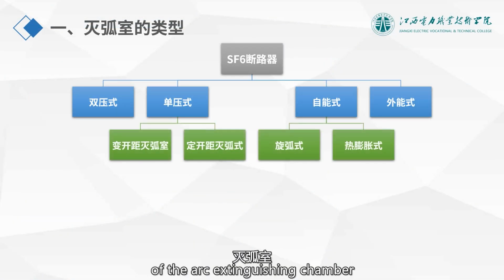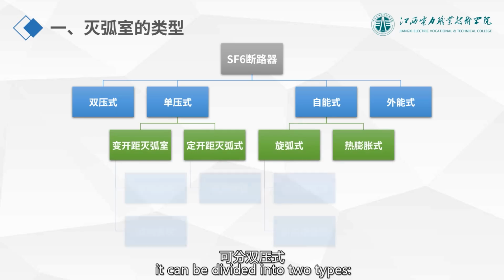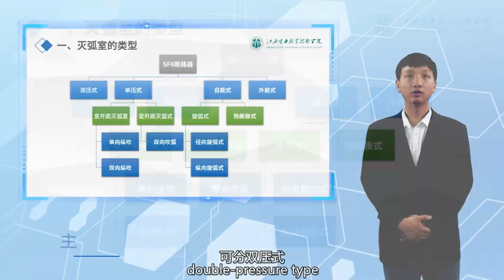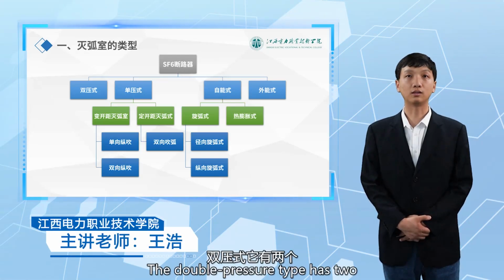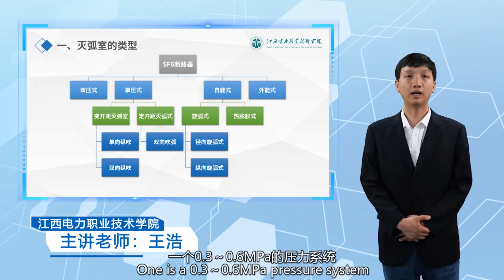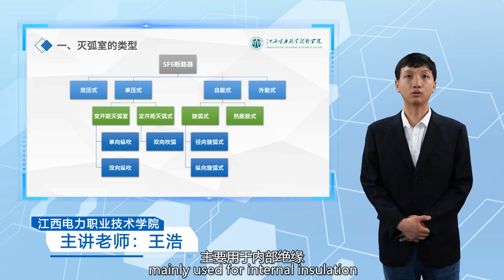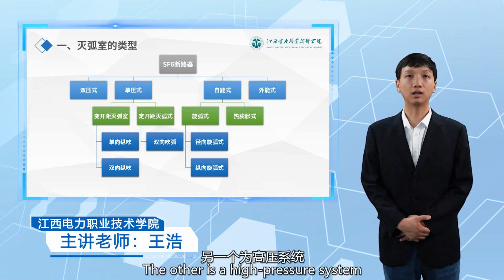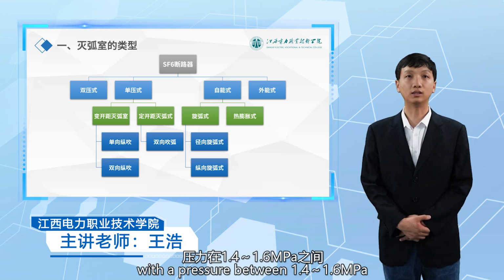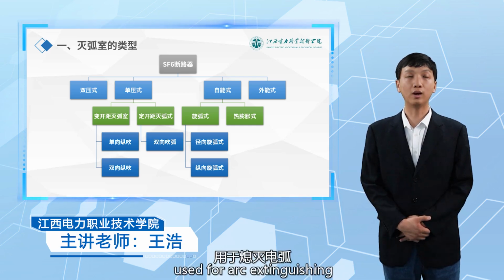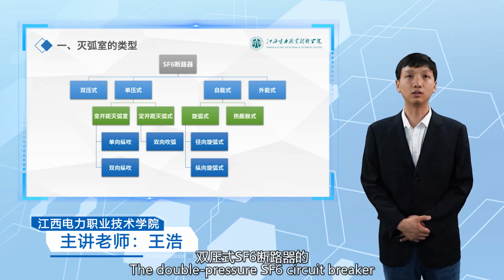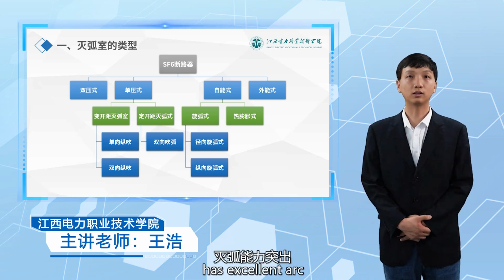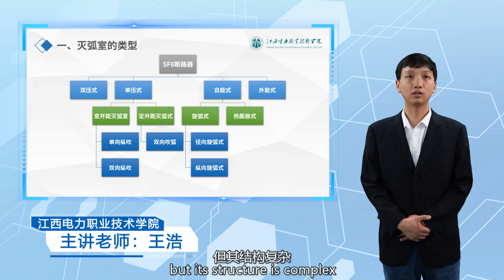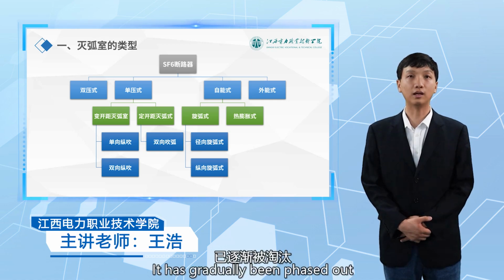According to the different structures of the arc extinguishing chamber, it can be divided into two types, double pressure type and single pressure type. The double pressure type has two pressure systems. One is a 0.3 to 0.6 megapascal pressure system, mainly used for internal insulation. The other is a high pressure system with a pressure between 1.4 to 1.6 megapascal, used for arc extinguishing. The double pressure sulfur hexafluoride circuit breaker has excellent arc extinguishing capabilities, but its structure is complex with many auxiliary devices. It has gradually been phased out.